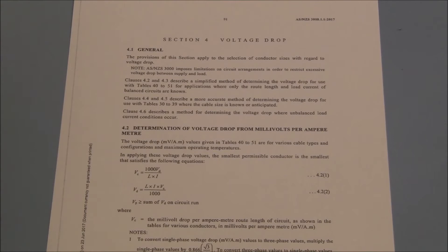The voltage drop equations are listed in Section 4 of AS3008. As we are seeking the value of VC, we will use VC equals VD multiplied by 1000 all divided by length multiplied by current.